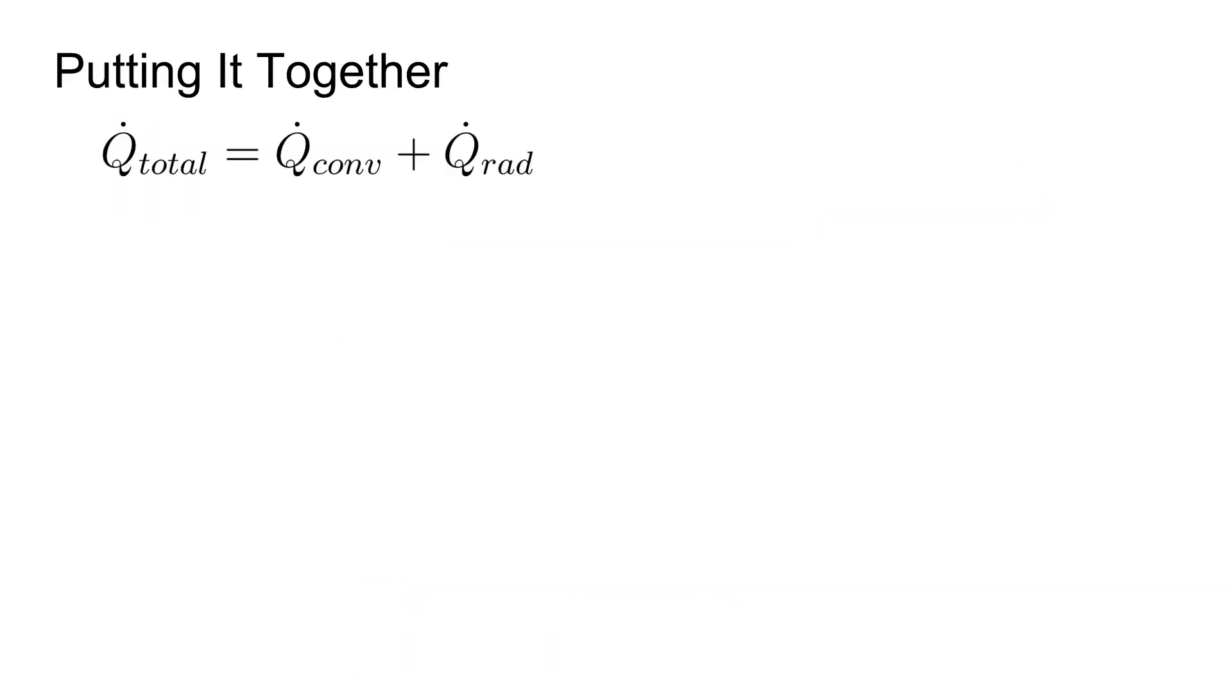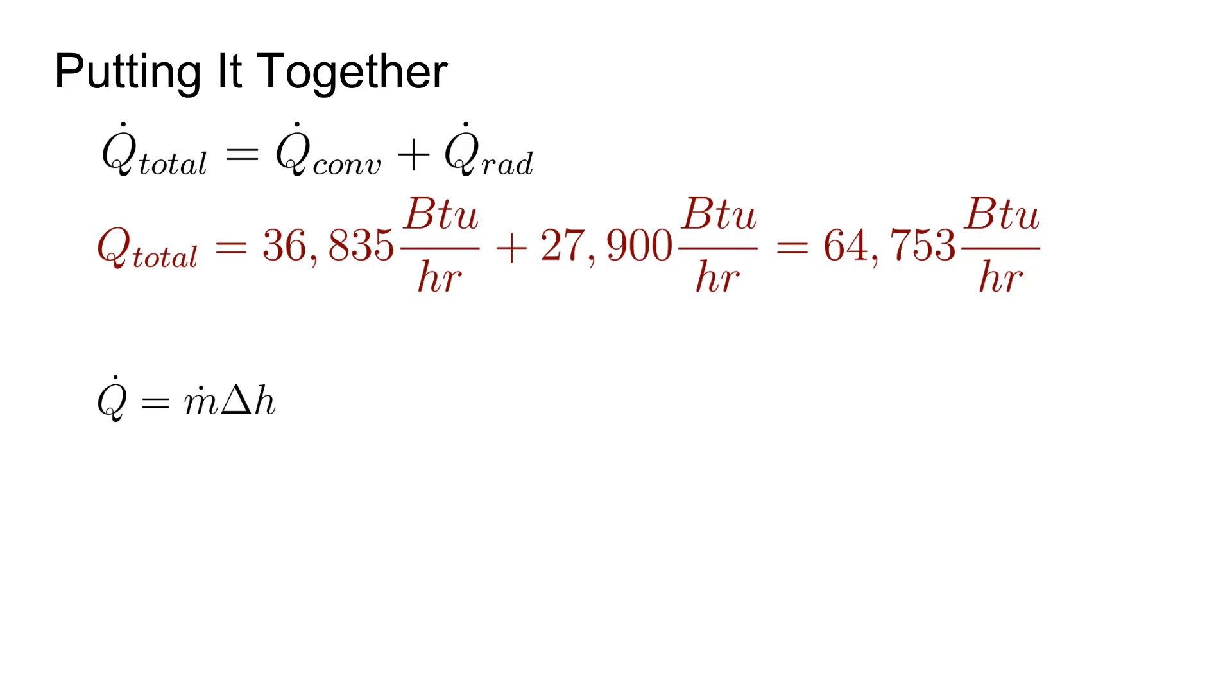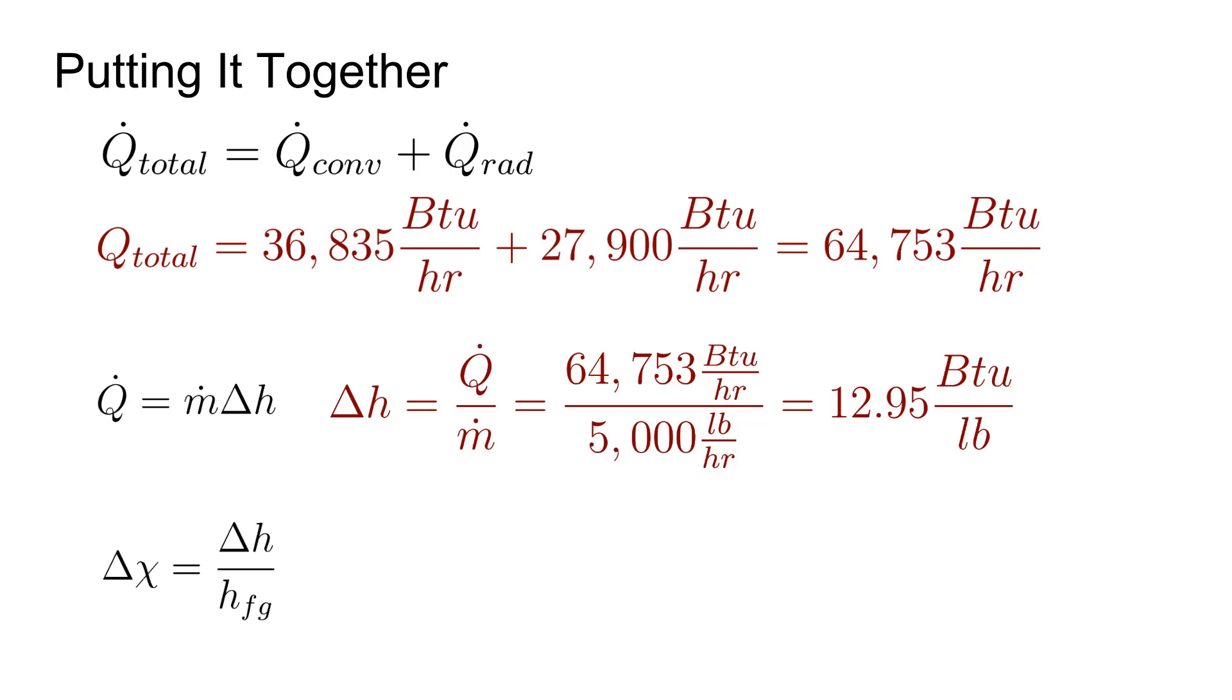To put it all together, according to our original game plan, we can add the heat loss from convection and radiation. That's nearly 37,000 BTUs per hour for the convection and nearly 28,000 BTUs per hour for the radiation for a total heat loss of some 64,000 BTUs per hour. Now we want to know how much that heat loss actually changed the enthalpy of the steam. To determine that, we write q dot equals m dot delta H, and rearrange that for delta H, then substitute the total heat loss and mass flow rate, and we get 12.95 BTU per pound as the change in enthalpy in the first 50 feet of pipe.